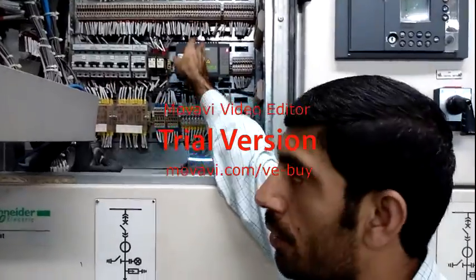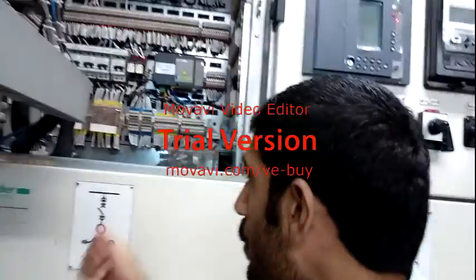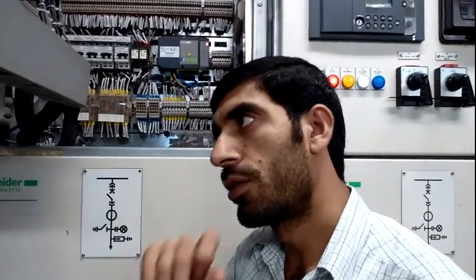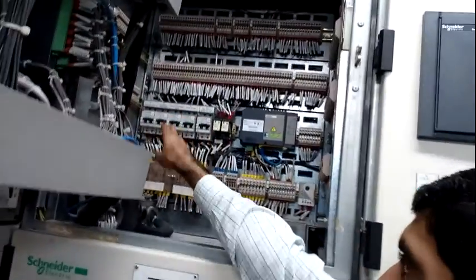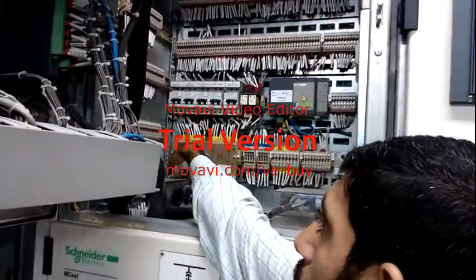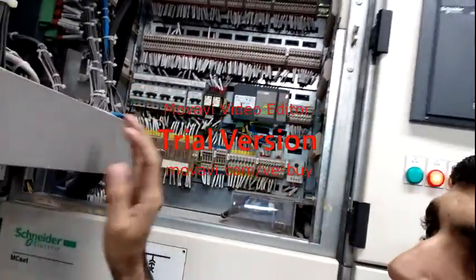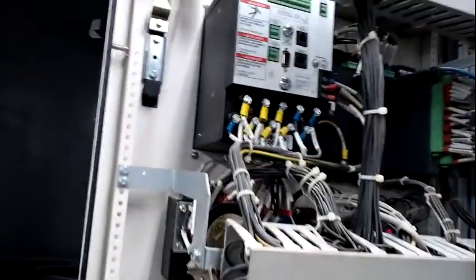This is for the transducer module, for signals and for rating. This is for SCADA. We use this for SCADA through a modem cable. This modem cable goes to the SCADA panel, and then the SCADA panel goes to the CCB control building. Now I want to show you this terminal box, which is for CTs. You can see here, this is the CT terminal box, and these CTs are coming here to the multifunction meters and to the relay.